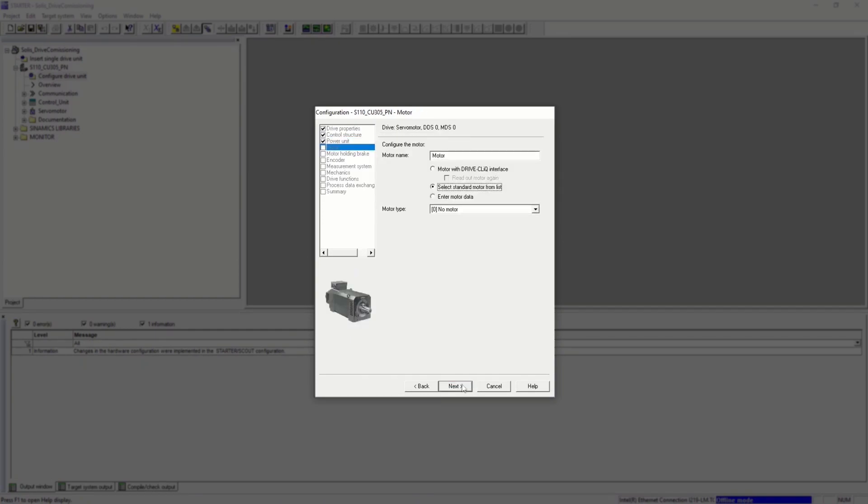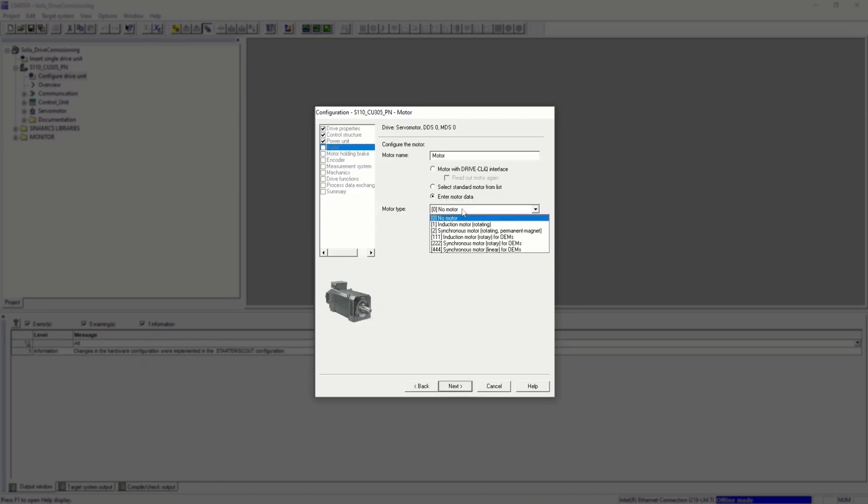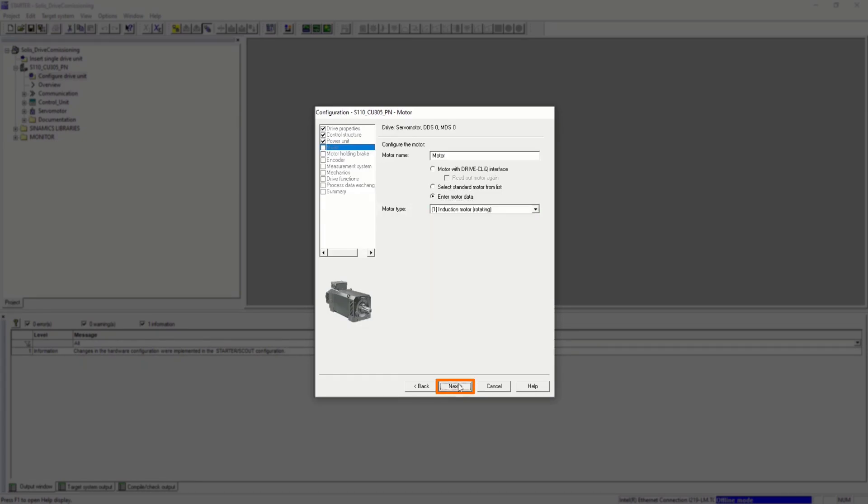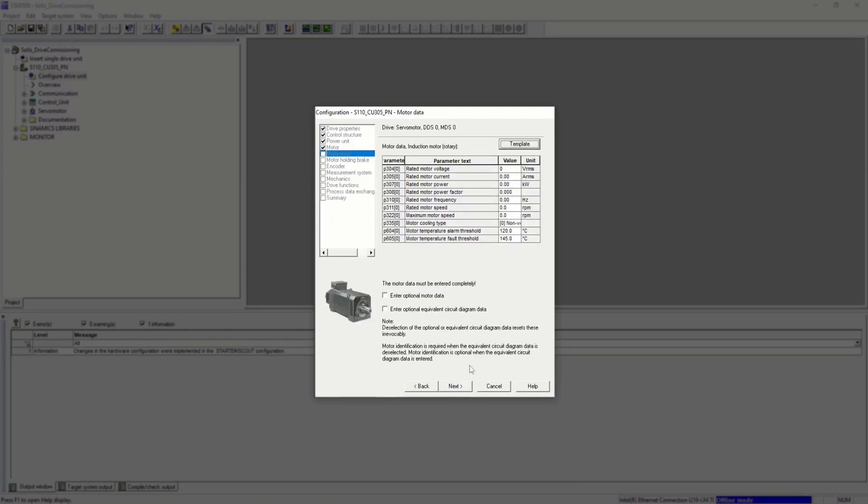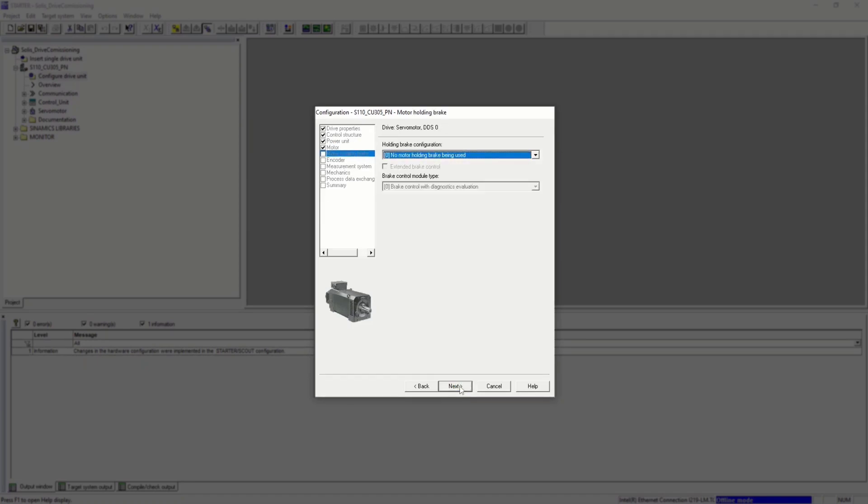Let's configure the motor type. The software has many kinds of motors. If you wish to configure an induction motor, this is what it would be like. You need all of these parameters. For this application, we're utilizing a servo motor with DriveCliq interface. All the motor parameters are sent from the DriveCliq interface, so we don't have to add any.